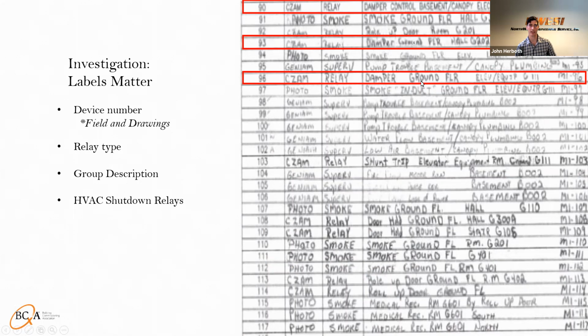But this is an example here. It says dampers, ground control elevator. That's really descriptive. Damper control per hall, G202. And that's just not very descriptive. It's descriptive for location, but not for what other dampers get triggered with that. So descriptions are really going to be critical in the programming to help you out in the field. Otherwise, you spend your time just triggering every single relay you can with a fire alarm contractor and going through and documenting the results. And that's a lot of field time.